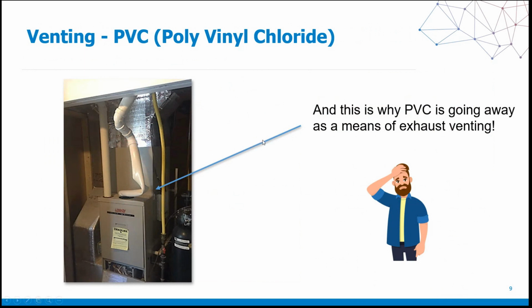So PVC as a means of exhaust venting is going away, and it's being replaced with polypropylene piping. And there are companies out there now that are producing polypropylene piping that is obviously made for these temperature tolerances that we're using them for, but also have proper gasketing material so that we no longer need to rely on glue and the cure times for those glues in the hopes that it cures in time before we have to actually put the system on. So very important to note.